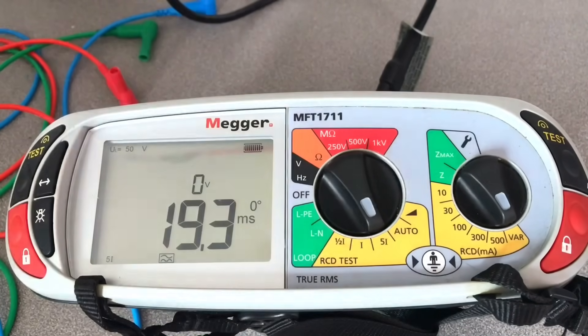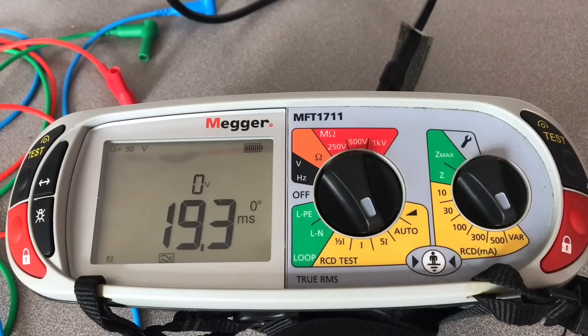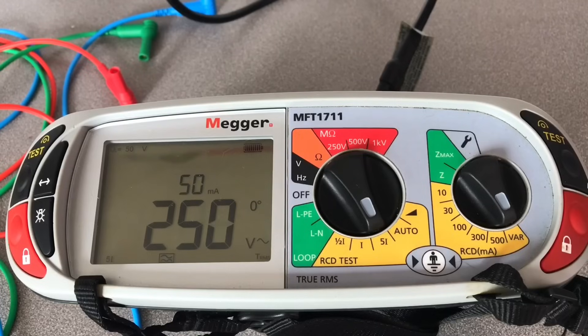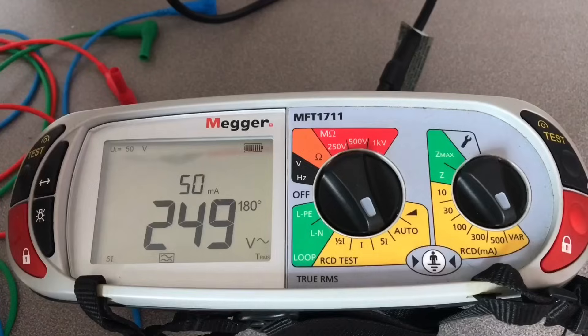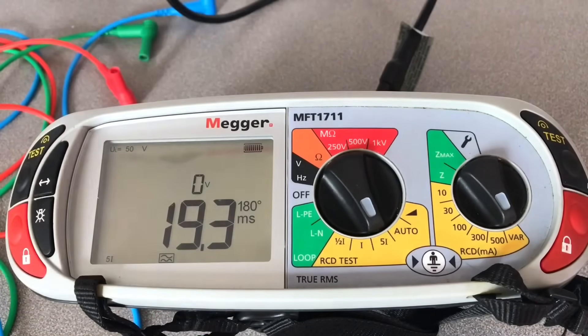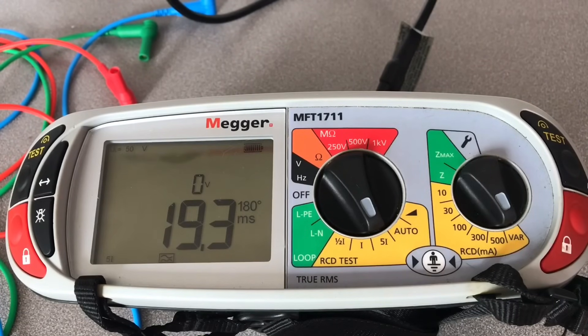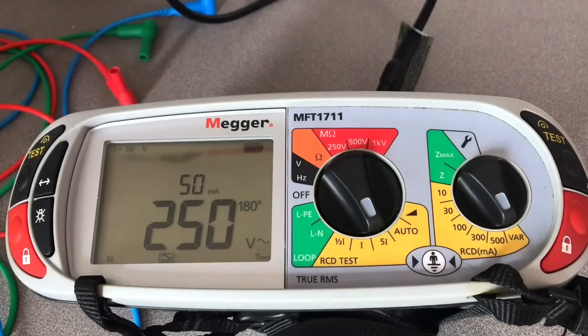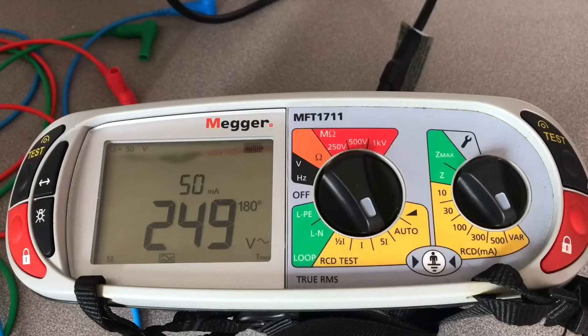Oh, that's a little bit more like it. 19.3. So that's now doing what the manufacturers require us to do, which is to pass the 250 milliamps through the RCD rather than the conventional 50. Do it on both sides of the cycle again. Okay, and we've got 19.3. So what we're really saying is that this is a fallback test. If we didn't work on a conventional test, that we can up it to five times 50 being the 250. Yeah, because it's not actually a recognized test practice as of yet in the United Kingdom. Okay, thank you.